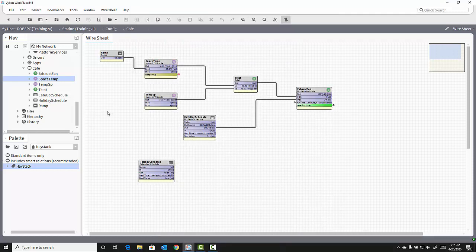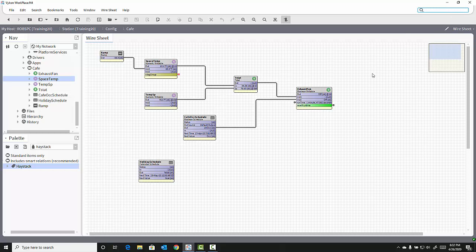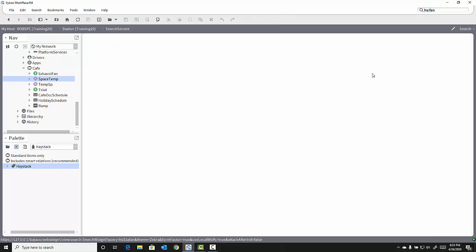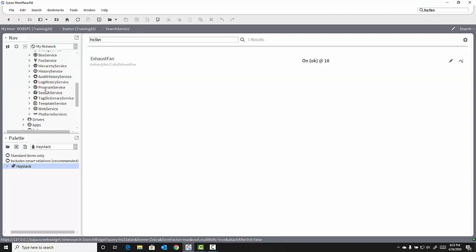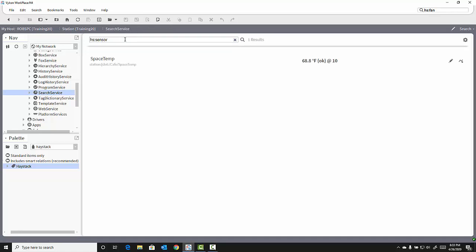To search for an object you've tagged, you can go to the Quick Search feature and type in the directory you want to search. HS stands for Haystack, and the tag you wish to search for. It will return all objects that have that particular tag associated with it. In this case, searching for HS fan returns my exhaust fan. Notice the Quick Search takes me to a service called the Search Service. That is the other way I can search for objects. Notice if I type in HS sensor, my space temp object is returned. That is because the HS sensor marker tag is part of the temp sensor tag group that I added to the space temp object.